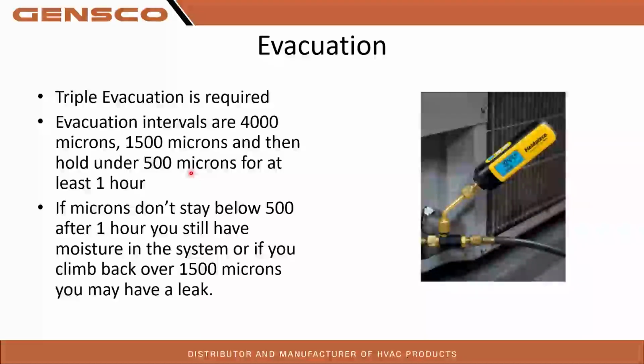Yep. So if you're struggling to find a leak, definitely test your equipment. Make sure your gauges and your hoses and all that kind of stuff is not causing problems. I too have had Fieldpiece digital gauges that had leaks in them and had to send them back to Fieldpiece to have them repaired, and they will do that. So if you have any issues like that, reach out to the manufacturer of your equipment and see if they can do some repairs for you.